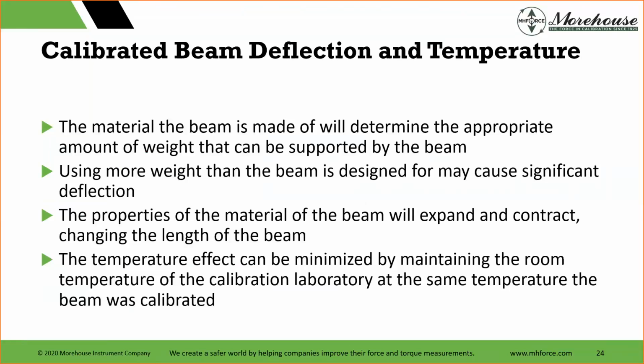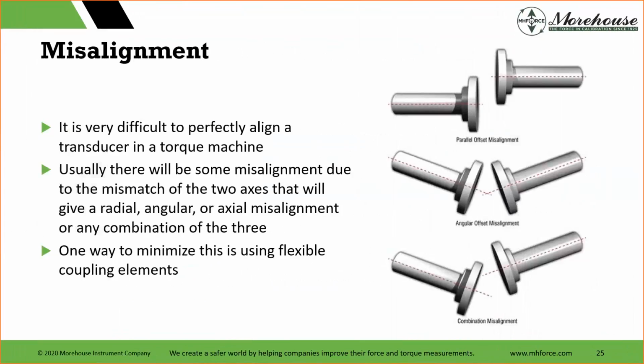So the material the beam is made of will determine the appropriate amount of weight that can be supported by the beam. People tend to do this: they want to use a big beam and go lighter. They don't want to account for temperature. Using more weight than the beam is designed for may cause significant deflection. Not good. The properties of the material of the beam will expand and contract, changing the length of the beam. That's a temperature error right there. And then the temperature effect can be minimized by maintaining the room temperature of the calibration laboratory at the same temperature the beam was calibrated. So if you have a beam that was calibrated at 20 degrees C, you should probably maintain your lab to plus or minus 1 degree C, if not better. And all that depends on what type of uncertainty you want to claim.